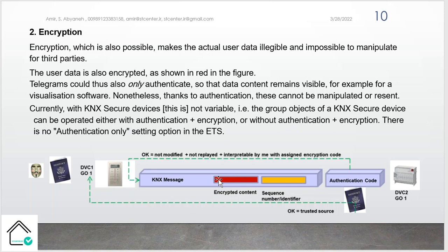Telegrams could also be only authenticated so that the data content remains visible, for example for visualization software. Nonetheless, thanks to authentication, these cannot be manipulated or resent. Currently with KNX Secure devices, this is not variable - it means the group object of a KNX Secure device can be operated either with authentication plus encryption, or without authentication and encryption. There is no authentication-only setting option in ETS. So nowadays, when a message wants to transmit in KNX in secure mode, it is equipped with both authentication and encryption abilities.